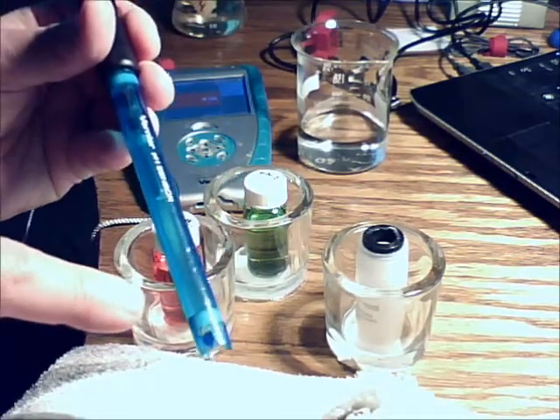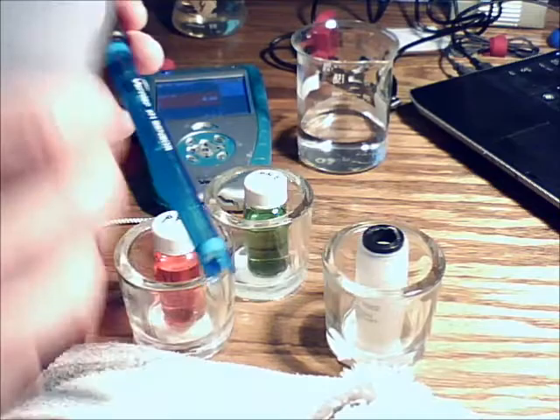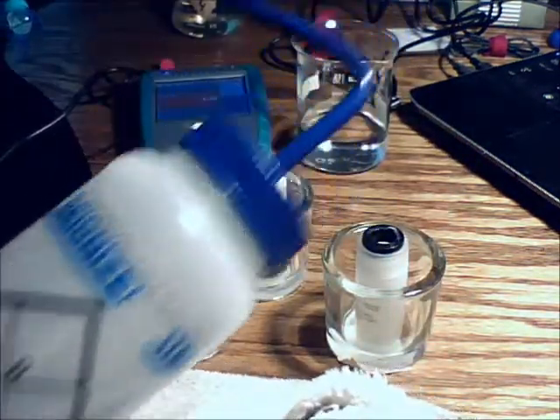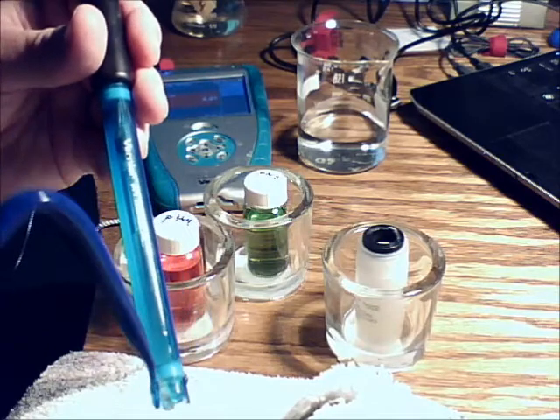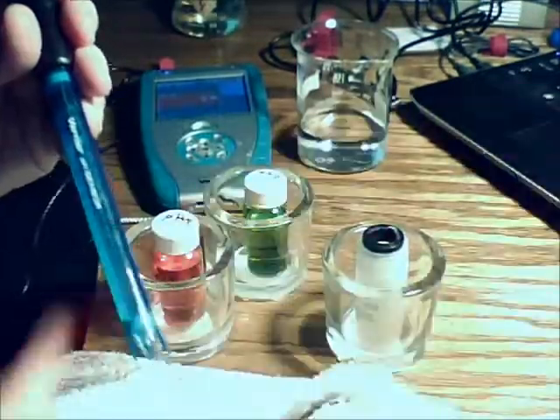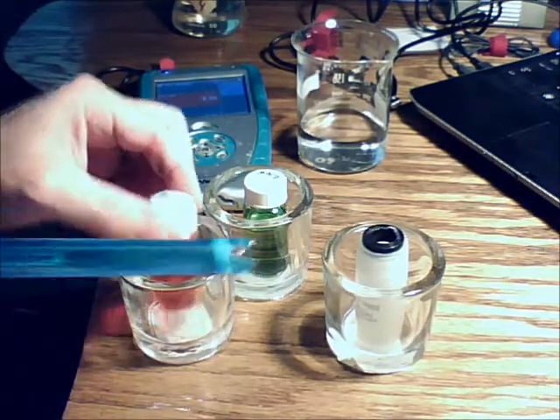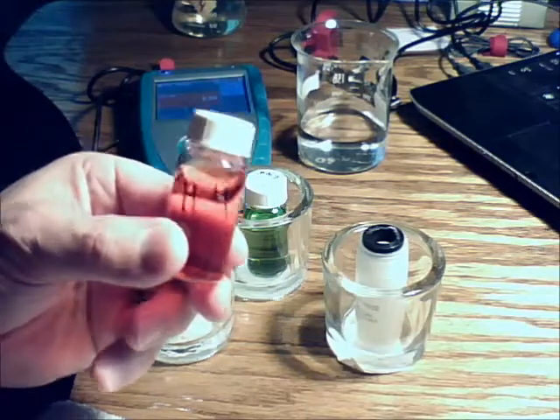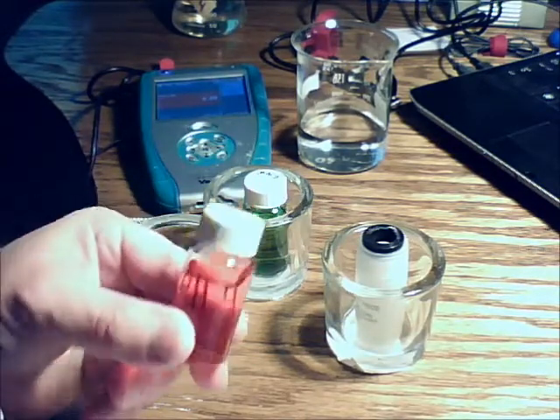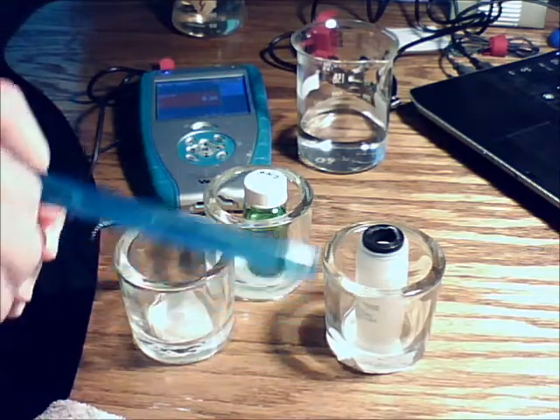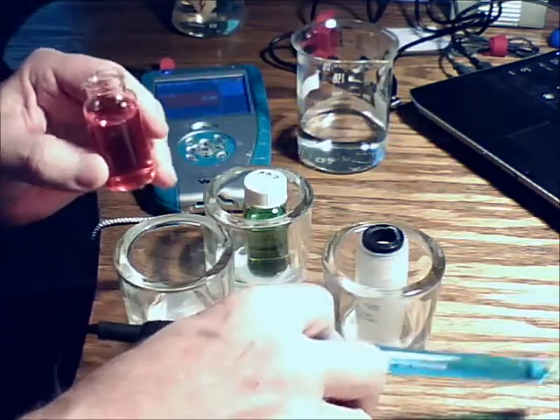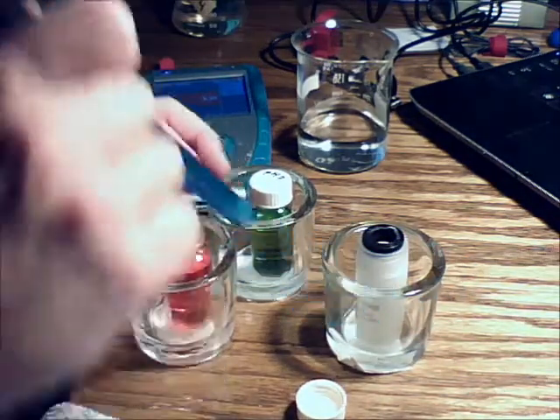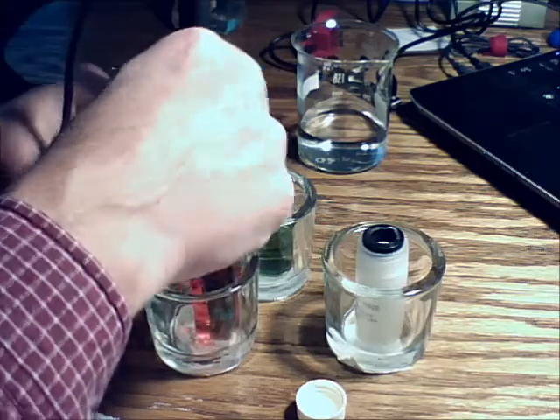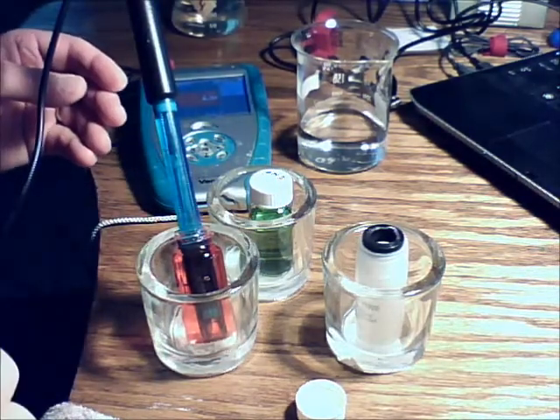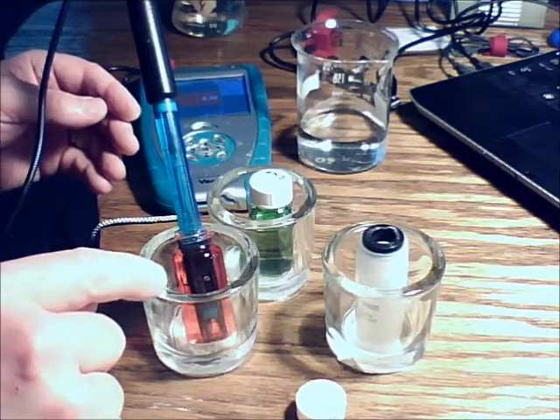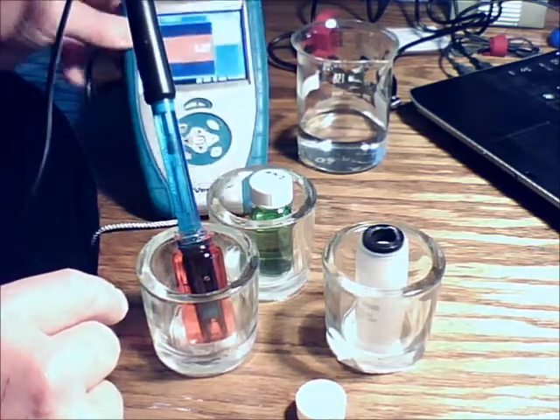Now, right now this is coated in a salt with a certain pH. We want to clean that off. So we're going to use distilled water. Okay? Every lab table's got deionized water, distilled water. And we're going to rinse that off really good. Okay? And then what you want to do is to calibrate. Now we're going to start by calibrating. It doesn't really matter which one you start with. But I want to start with a pH 4 buffer solution, okay? pH 4 buffer solution. So what I'm going to do is take the top off. And by putting it in this candle holder, it keeps from tipping over. I can just slide it right down in there. Now what I did was to rinse the tip of this pH meter off. Okay, then shake it off and then put it in here. Got it? And then what we're going to do is go over here to the LabQuest.